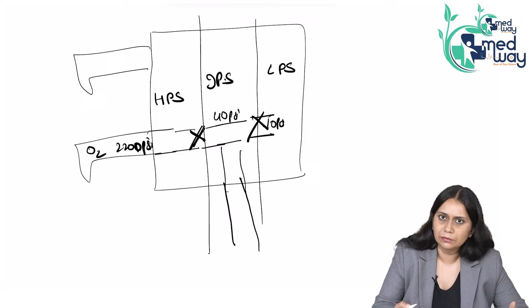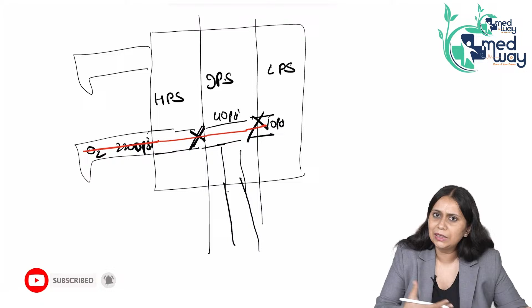Before passing through this pressure regulator, this was the high pressure system. Now it is 40 psi and your pipeline meets at this point after the first pressure regulator. So, it is an intermediate pressure system. Now, after this it passes again through the second pressure regulator. Again the pressure reduces to 10 psi which our lung can tolerate. So, now it is in the low pressure system. So, from high pressure to intermediate pressure to low pressure. These are the three parts in which the machine is divided.